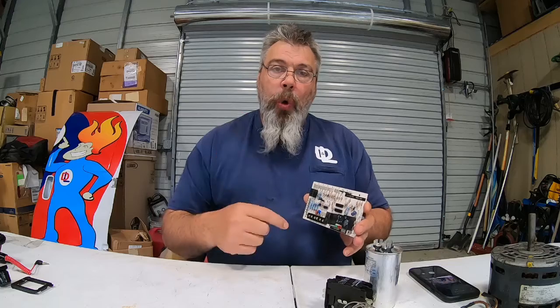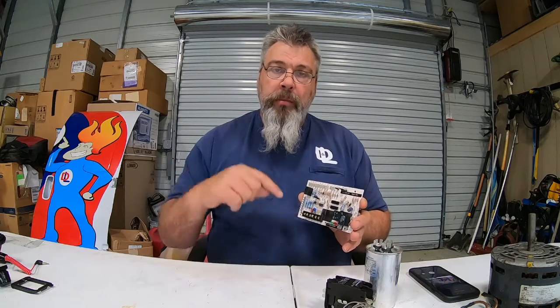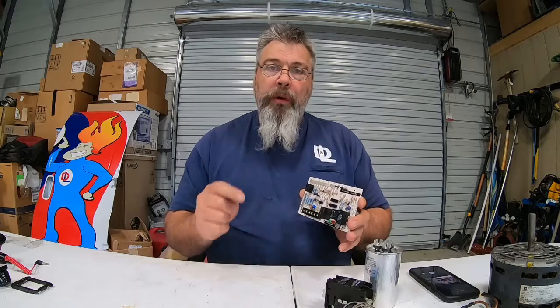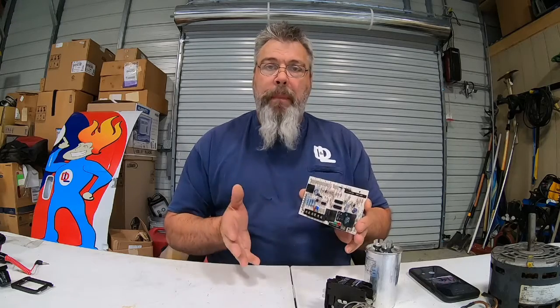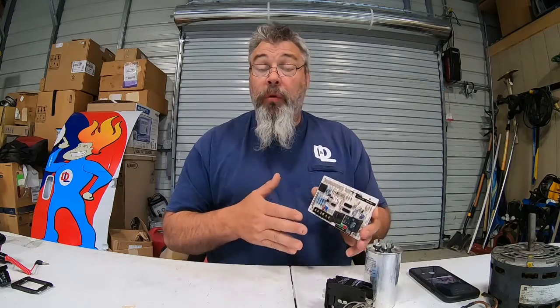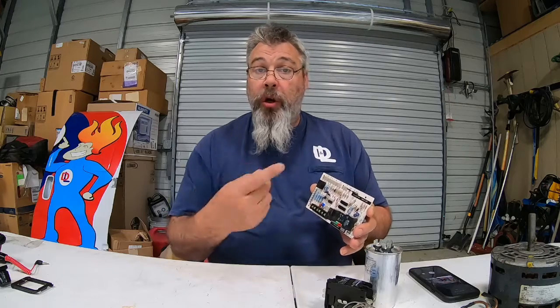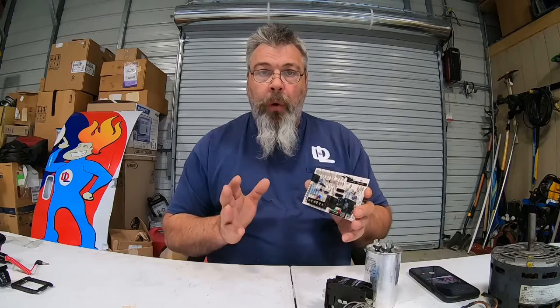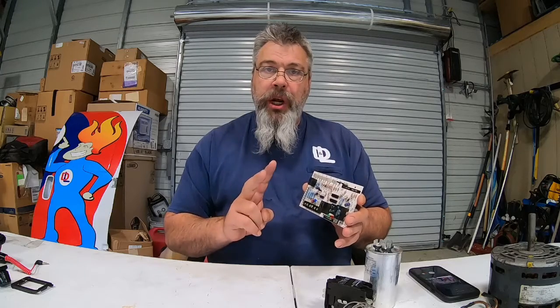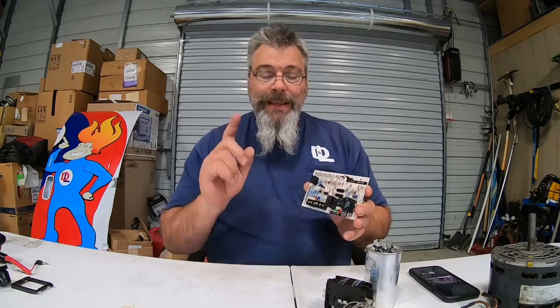And because we take the heat from the outdoor air, if that air is colder than it is supposed to be, then our refrigerant is going to be colder. We never want our refrigerant to get below freezing, because what happens is our outdoor unit will freeze up. It'll start to get frost on the coil, and it freezes and freezes and freezes till it gets to a point. Two things initiate it: time and temperature.